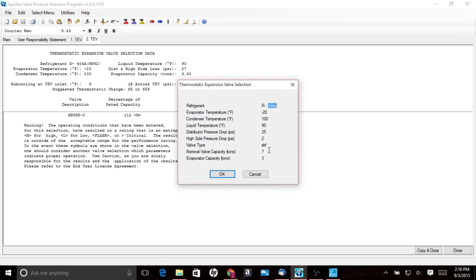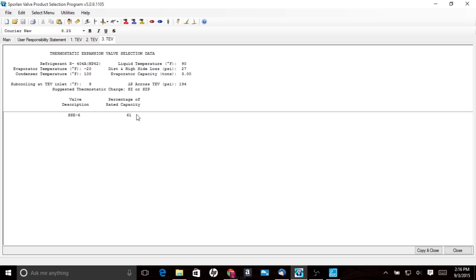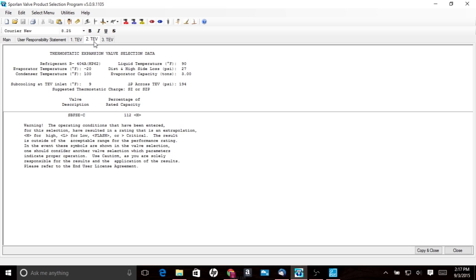So at this point, we're going to go back and we're going to show you, if you put in the same information with just an S-body valve, it's going to spit out an SSE6 and percentage of rated capacity is 61. And we see that there are no warnings here. You have subcooling is your pressure drop across your expansion valve. And this is a nominal rating of the evaporator, you know, all the stuff that we put in, it spits out this valve. So this was the original valve that I was looking to order. When I did contact the manufacturer, they suggested going with the four, which was there based on their calculations. So we decided just to put the four in there and go with the manufacturer's selection criteria. If we hadn't wanted to go in with the six, it would have been fine. Not a big deal.